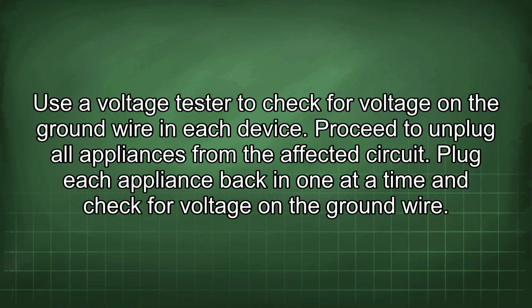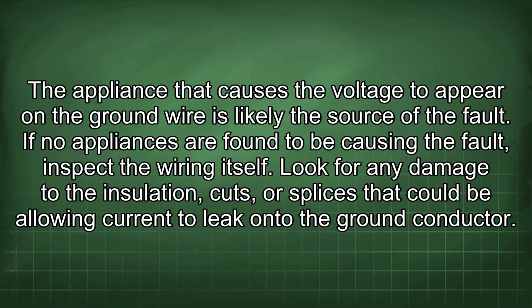Proceed to unplug all appliances from the affected circuit. Plug each appliance back in one at a time and check for voltage on the ground wire. The appliance that causes the voltage to appear on the ground wire is likely the source of the fault. If no appliances are found to be causing the fault, inspect the wiring itself. Look for any damage to the insulation, cuts, or splices that could be allowing current to leak onto the ground conductor.